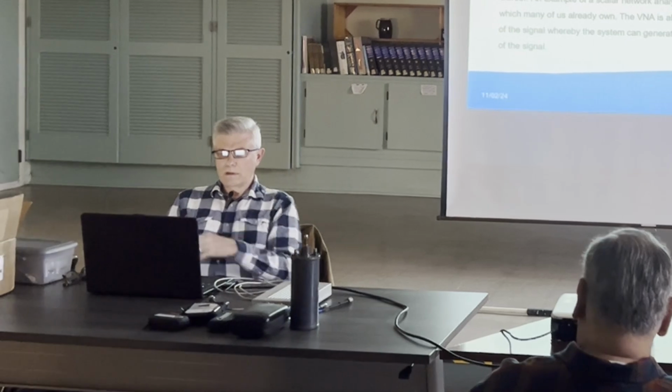I run a company called Broadcast Devices Incorporated, and we make, among other things, RF power meters. And we often have to sweep the directional couplers that we use in those power meters, and a vector network analyzer is used to do that. So that's just one use, and I've got a few of those with me today that I can show. And so anyway, let's just get started with this.